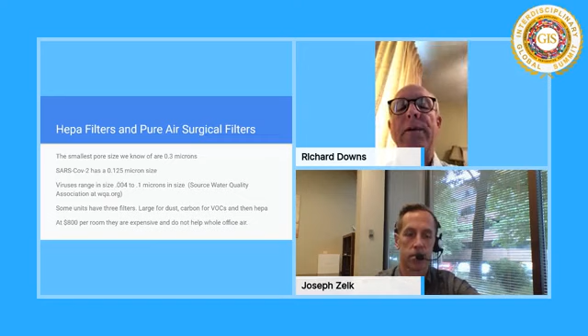Let's move on to HEPA filters, which we talked about before. Pure air surgical filters have a micron size, and the smallest I've ever seen are 0.3 microns. That's too large to filter out viruses. The SARS-CoV-2 virus, one of the larger ones, has a size of 0.125 microns, and it still goes easily through these micron-size HEPA filters.